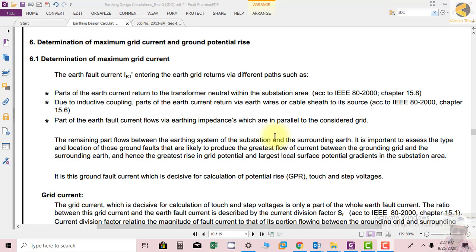In this section we are calculating the maximum grid current. The fault current entering the grid returns via different paths. Parts of the earth current return to the transformer neutral within the substation area, according to IEEE 80-2000 Chapter 15.8. The transformer neutral becomes a point where earth fault current flows back.